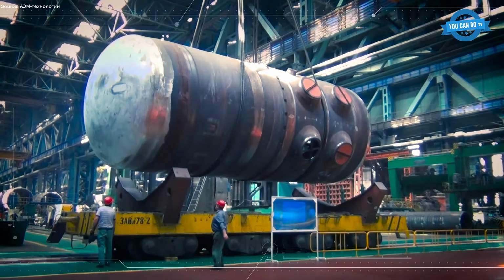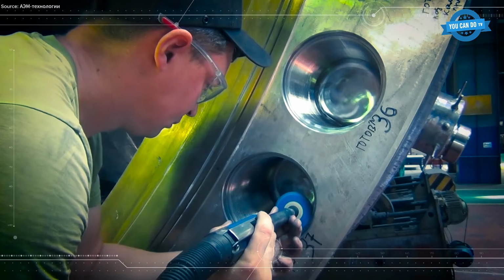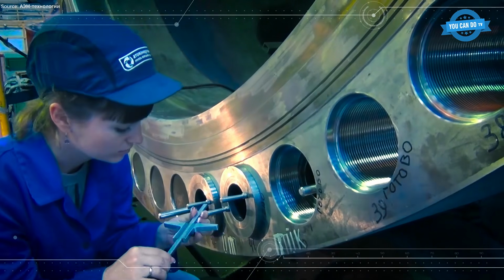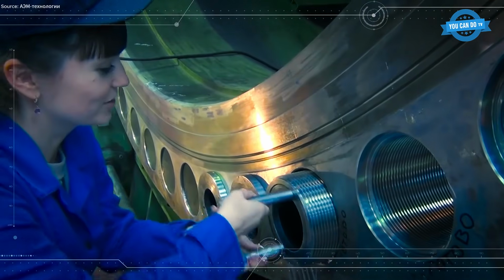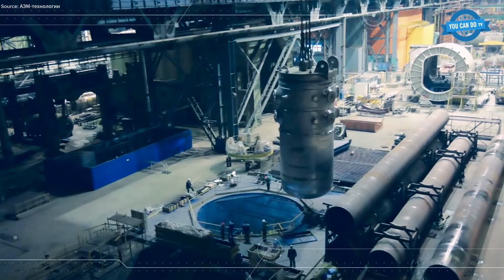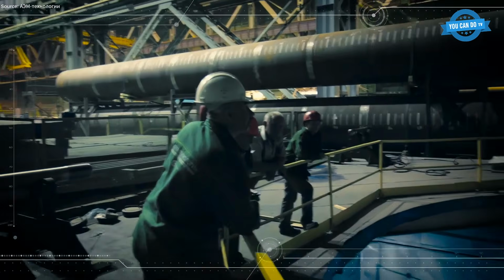After forming, components undergo extensive mechanical treatment, plating, assembly, and multi-pass welding. Heat treatment relieves residual stresses, followed by X-ray inspection and hydraulic pressure testing. Only after full verification is the reactor vessel approved for delivery.